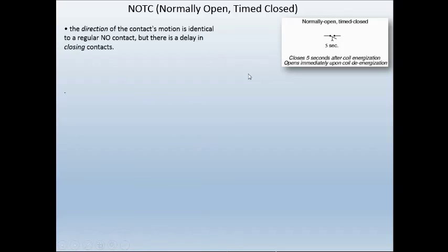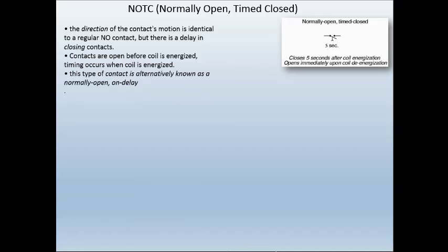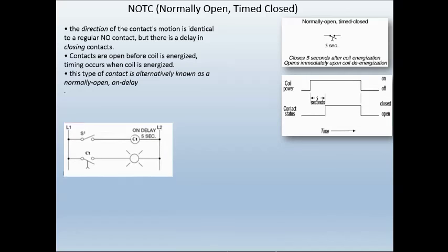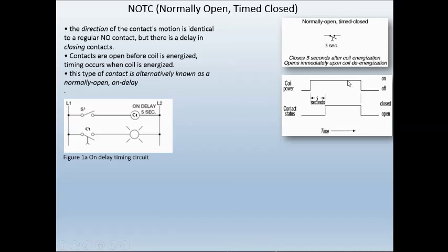Let's talk about a normally open timed closed. This is the symbol for a normally open timed closed. The contact is shown in open position. The direction of the contact's motion is identical to a regular normally open contact, but there is a delay in the closing of the contact. When we look at this picture, we see it come down like this and there's an arrow pointing up — that is the direction of the delay. So it means that after five seconds, it's going to close. The contact will move up.